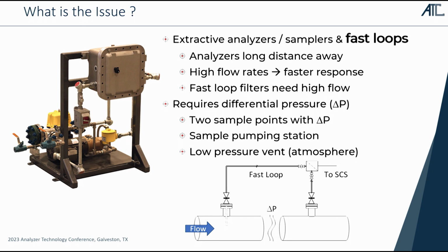And so, if we look at this, let me just see if my pen's working here. No, it's not. Okay. If you look at that figure in the bottom, you can see if we have a direction of flow, we have some differential pressure, and we've got a high pressure point and a low pressure point, it's pretty easy for us to get continuous flow through this loop. So I got this thing positioned, okay? But it's going to require some differential pressure.